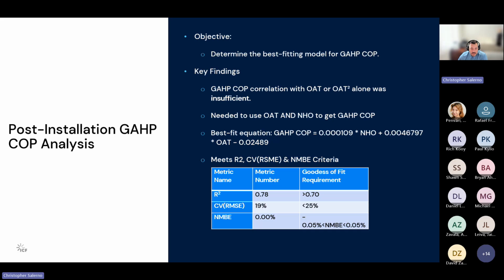We found a reasonably good fit at a 0.78 R squared, 19% CVRMSE, so a pretty tight spread, and then obviously a 0 net mean bias error. So it meets all the criteria. And so in the baseline, if you remember, we really just used the net heat output to determine the baseline consumption. Here we're using the gas absorption heat pump equation, using net heat output and OAT to be able to predict the performance of that. I also want to point out that the runtime of the GHP largely affects the COP, and we'll talk about that in a couple slides.